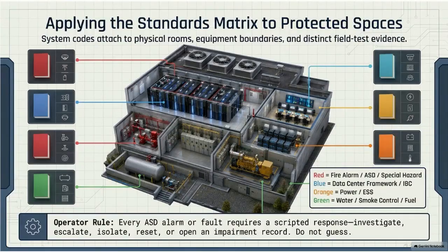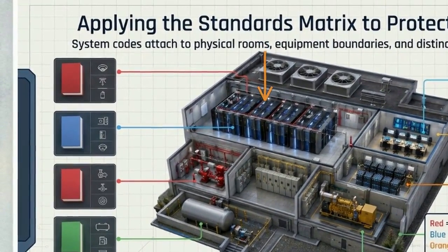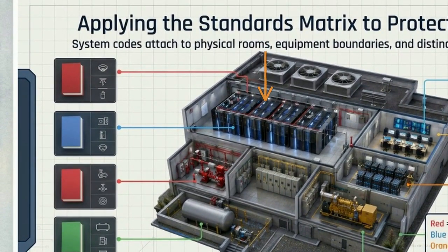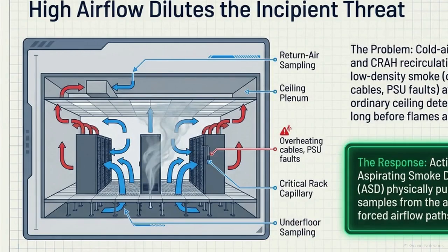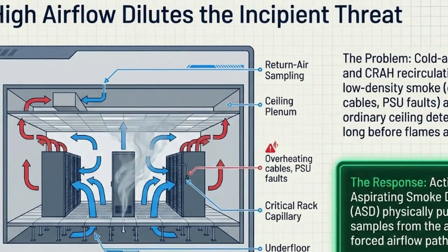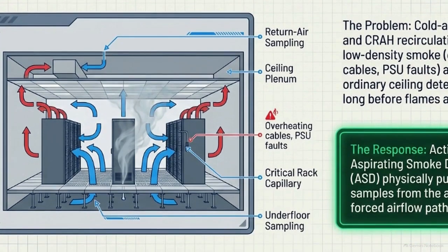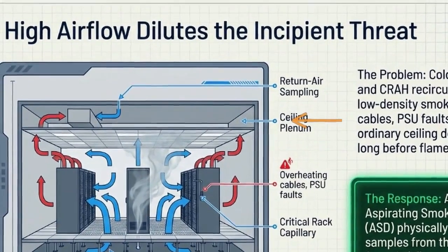This 3D layout maps how our standards actually attach to the physical building. Notice how the blue IT framework and the red fire alarm and suppression codes converge on the central data hall. This cross-section highlights a massive problem inside those halls: high airflow physics. Cold aisle supply and powerful recirculation units push massive volumes of air through the server racks. That forced air pulls low-density smoke, like the kind generated by an overheating cable or a power supply fault, away from traditional ceiling spot detectors. The threat is diluted before it ever reaches the ceiling plenum detection zones.